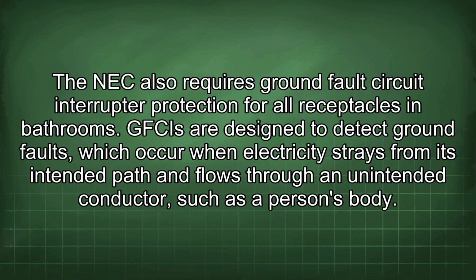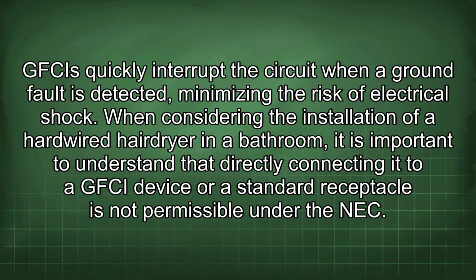The NEC also requires ground fault circuit interrupter protection for all receptacles in bathrooms. GFCIs are designed to detect ground faults, which occur when electricity strays from its intended path and flows through an unintended conductor, such as a person's body. GFCIs quickly interrupt the circuit when a ground fault is detected, minimizing the risk of electrical shock.